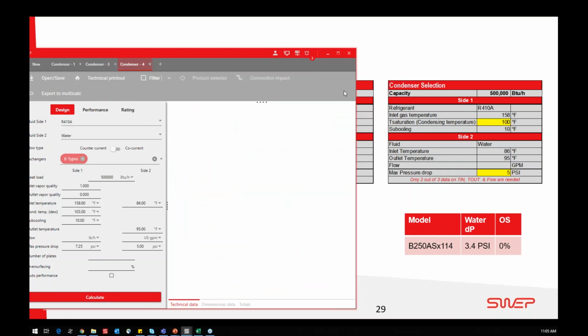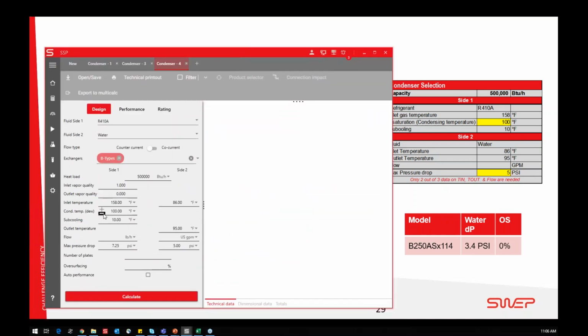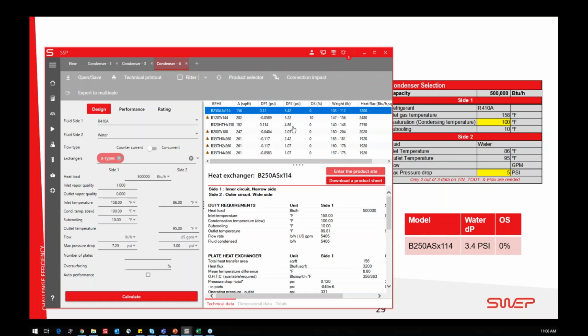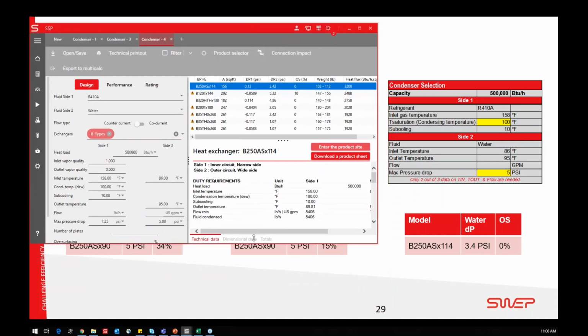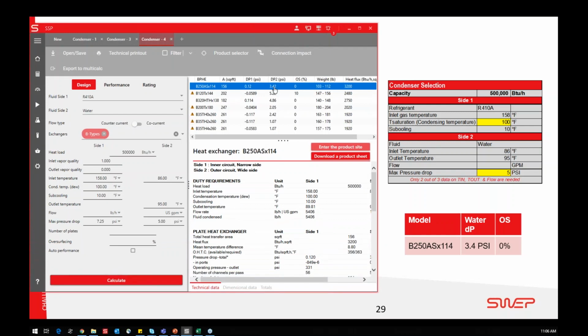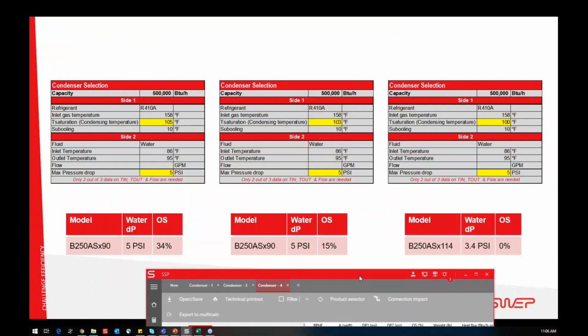So if we take the last one, now we're going to an even lower condensing temperature, from 103 to 100. And now we get a slightly bigger heat exchanger, up from 90 plates to 114 plates. Here it comes. Now the pressure drop, before it was 5, is now 3. So now it's not pressure drop restricted anymore. The over surface is down, meaning that the heat surface that we have added to this heat exchanger will meet the 100 degrees target condensing temperature. This is how pressure drop and thermal length or performance interact.